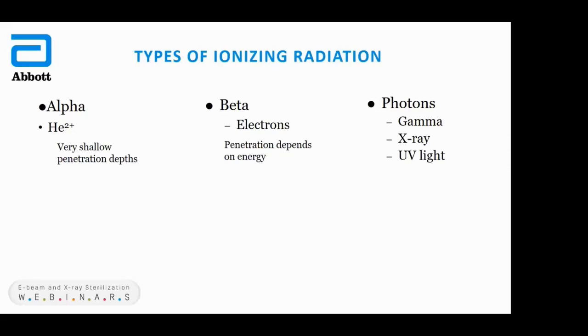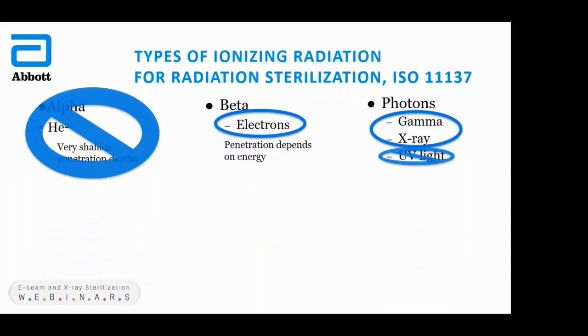So at the very beginning, when we talk about radiation sterilization, it's really ionizing radiation sterilization. This is the broad scope of ionizing radiation. The reality is for radiation sterilization per the standard, only three types are included, but all three are included: E-beam electrons, gamma, and X-ray.